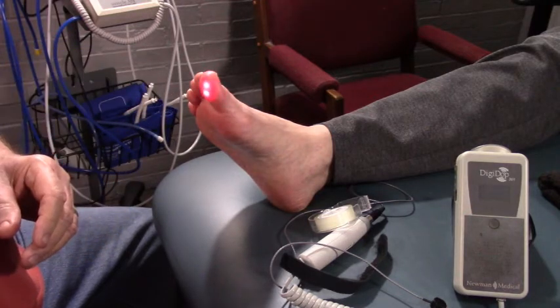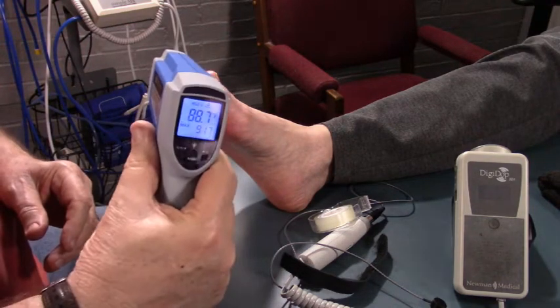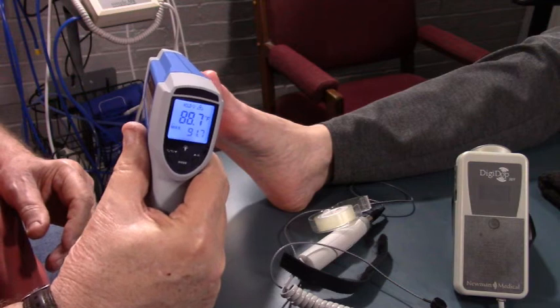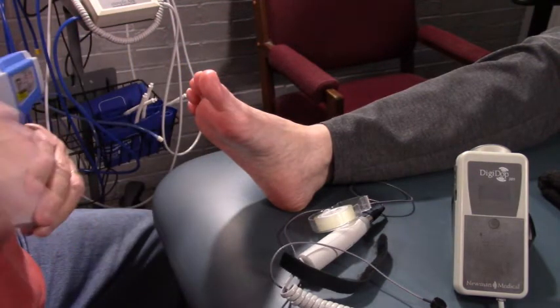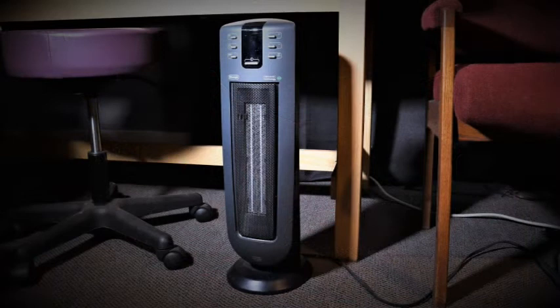There cannot be enough emphasis placed on the fact that the treatment room and the patient's toe need to be warm when performing a TBI. This is not only important, but also crucial to obtain a successful test. The lowest successful and trouble-free temperature is about 70 degrees for the digit itself. Often, an additional small heater in the room is necessary to accomplish this.